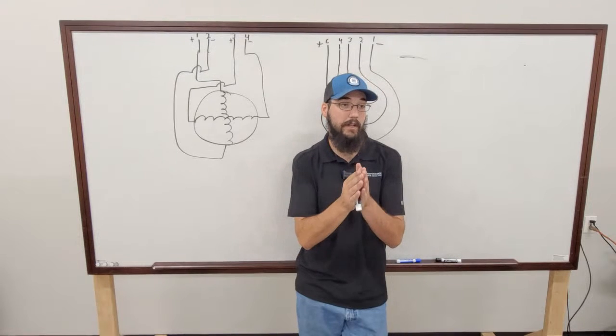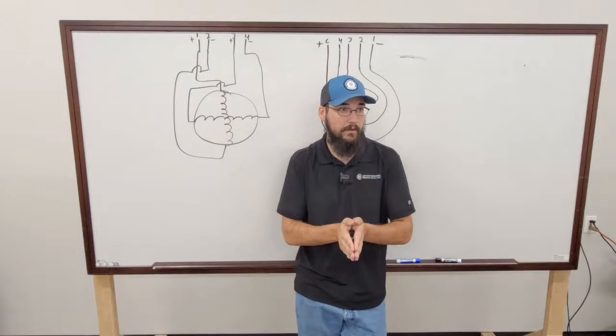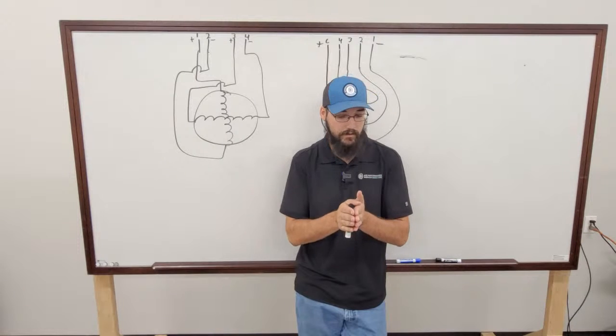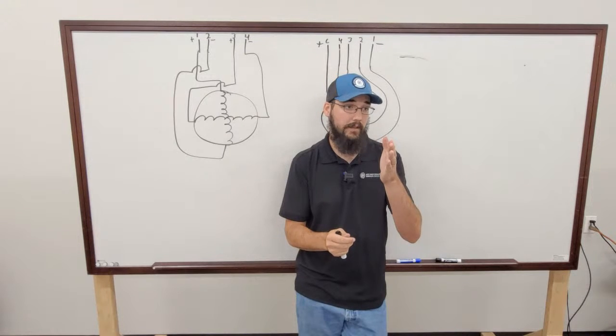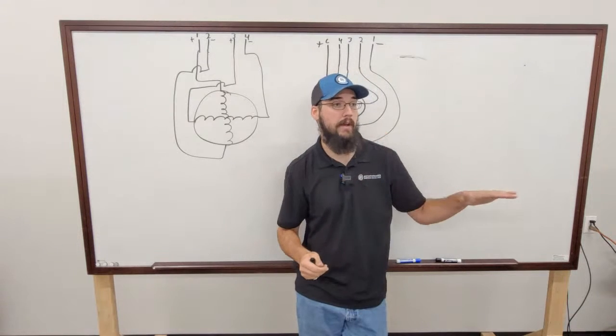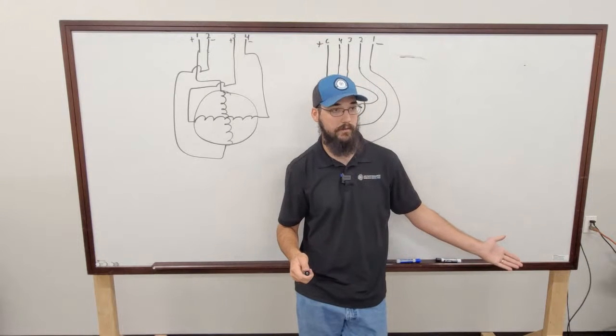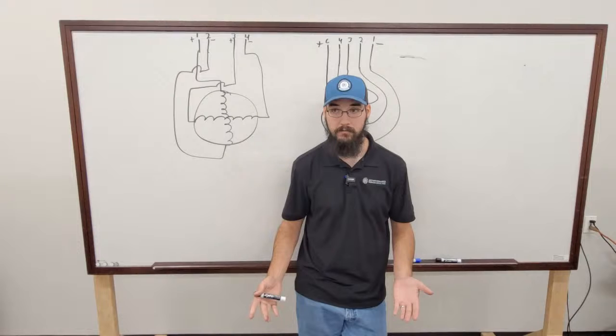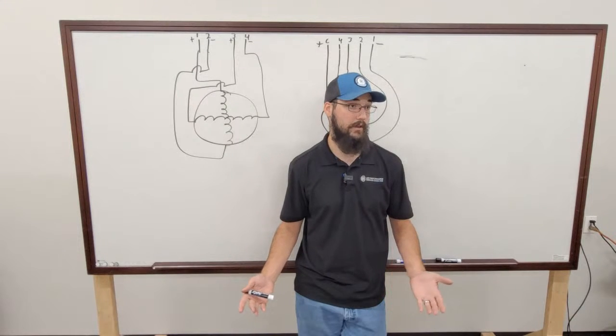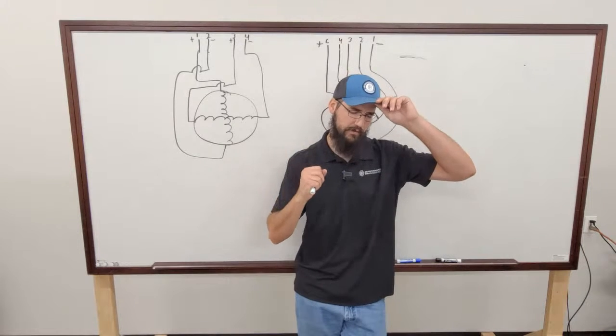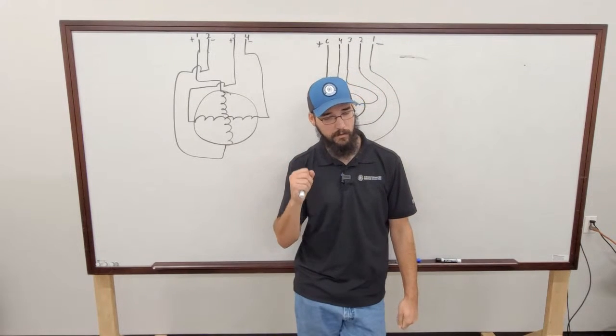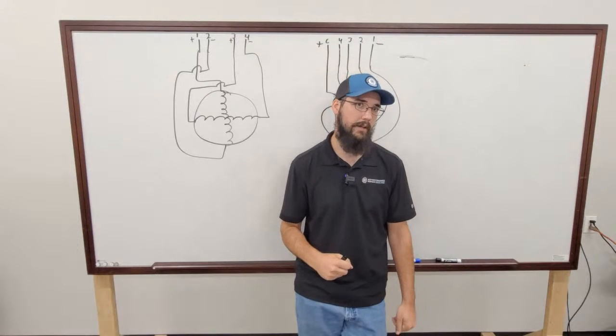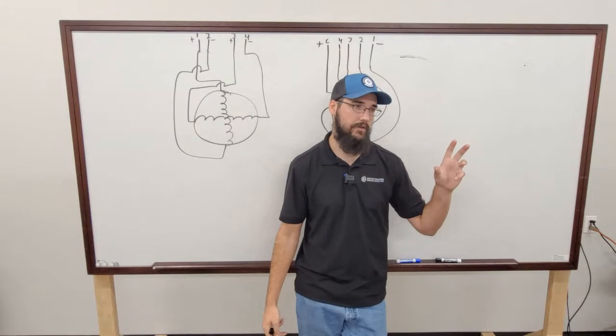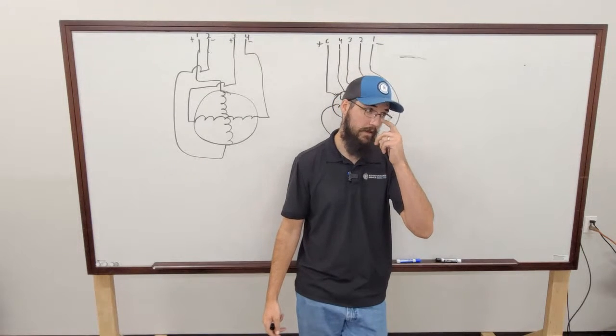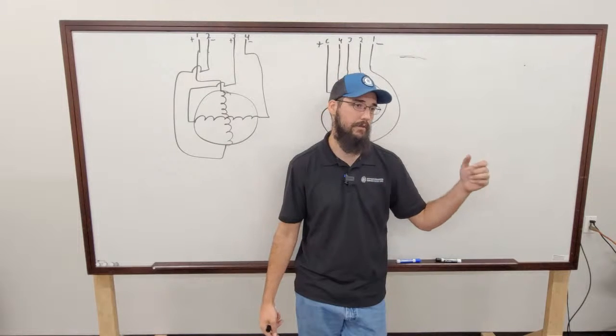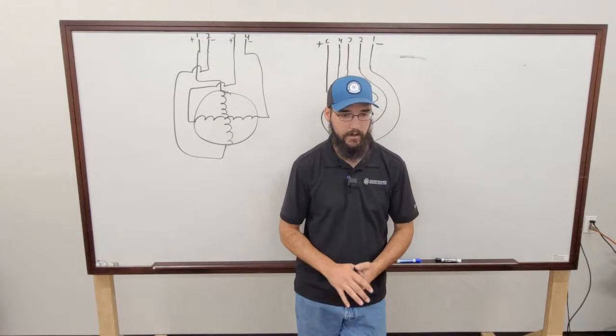That's how it's doing it: it's reading the temperature drop on the tip of that sensor, and it knows that by losing X amount of heat through that, I have Y amount of water flow. And those do have to be calibrated. They don't come out of the box, slap it in, and it's good to go. Well, I say that. Most of them have to be calibrated. Some of them, if you order them OEM, may come pre-calibrated. Like York, for example, the ones that they send you are the new series, not the old series. It's already preset. You don't even have an adjustment option. You just plug it in and go. So thank you, York, for that.